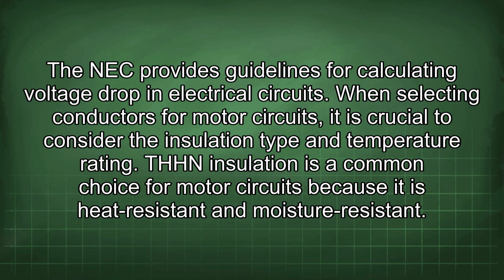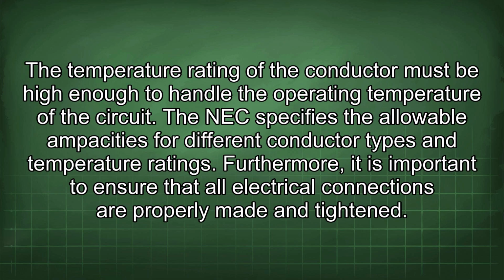When selecting conductors for motor circuits, it is crucial to consider the insulation type and temperature rating. THHN insulation is a common choice for motor circuits because it is heat resistant and moisture resistant. The temperature rating of the conductor must be high enough to handle the operating temperature of the circuit. The NEC specifies the allowable ampacities for different conductor types and temperature ratings.